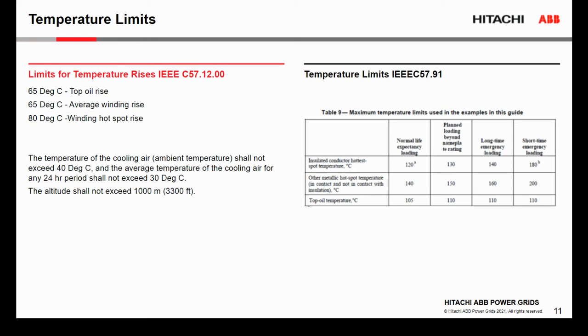So both those insulation systems have temperature limits, and to make sure that we don't reduce the life of the transformer, we want to make sure the hotspot rise over the ambient inside the transformer will not exceed 80 degrees C. The top oil rise will be limited to 65 degrees C. And those temperature rises are based on the 24 hours average rise, ambient temperature of 30 degrees C.